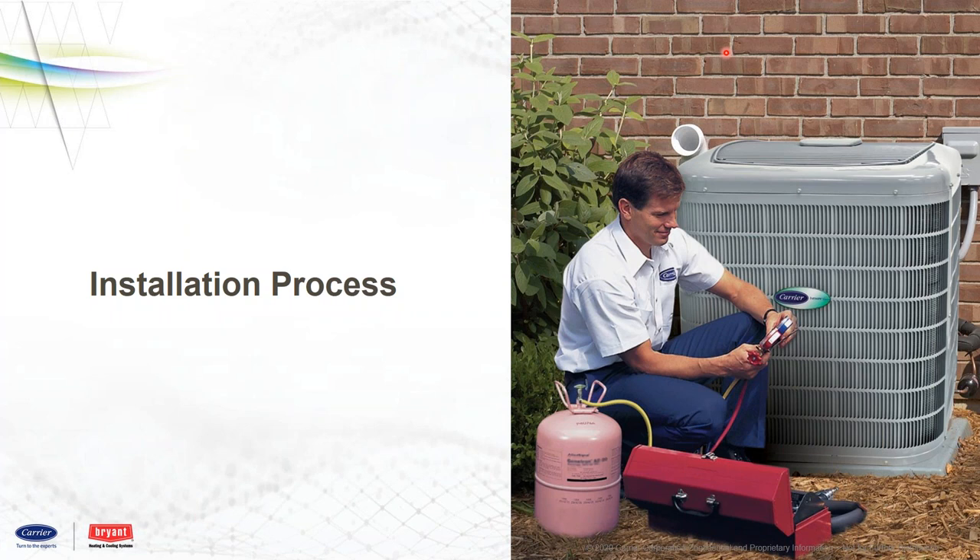Now let's start talking about some of the installation process. The products we just mentioned — AC and heat pump on both Carrier and Bryant — these have to operate with an Infinity or Evolution Connex system. You have to have a communicating indoor furnace or the EPI fan coils. You have to have the Infinity or Evolution Connects controller. There is just no way to operate this without it.